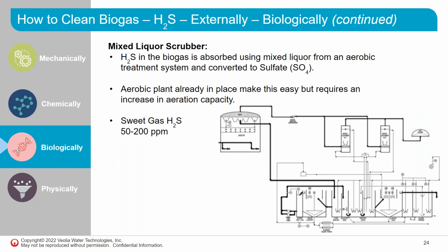The mixed liquor scrubber. This would be a very good integration to your biogas system if you have a downstream aerobic system available. The concept here is somewhat similar to Sulfothane that we discussed a bit earlier, but here we use an aerobic mixed liquor to absorb and oxidize sulfides. So you do not need a separate digester because you already have an aerobic system. But you may need to increase the aeration capacity a little bit to accommodate the sulfur oxidation. But this is also a very good method that you can use to remove or scrub H2S from your biogas.